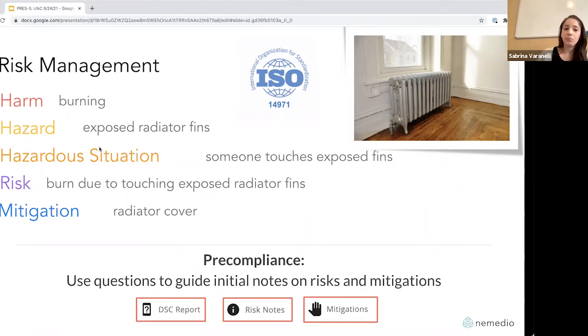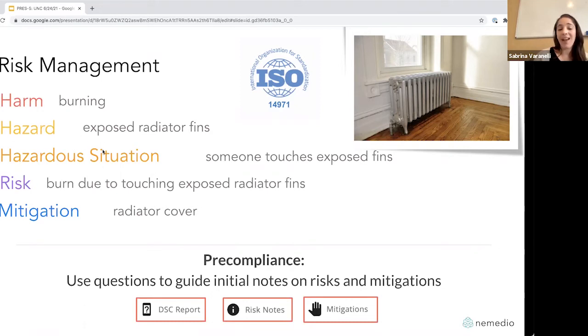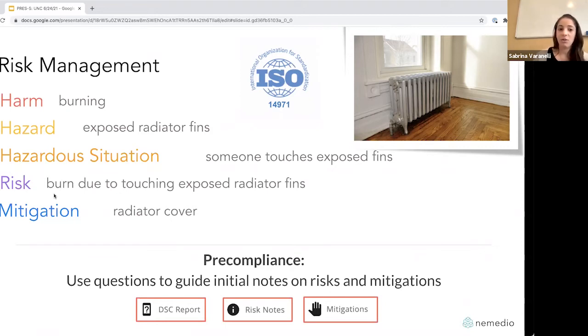When we look at harm, we consider its severity. A bruise is less severe than a laceration; a first degree burn is less severe than a third degree burn. So we're qualitatively looking at severity levels of harm and probability levels of that harm occurring to a patient. From an academic perspective we do the exercise of formally assessing the risk — but as normal everyday engineers, you already know there's a risk.